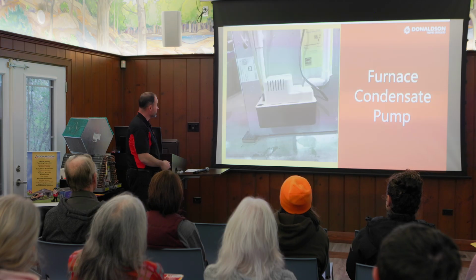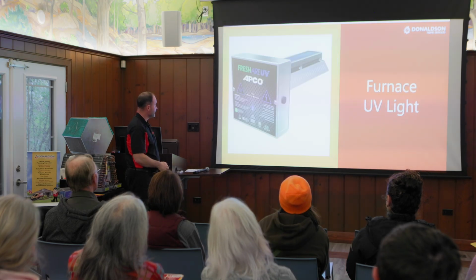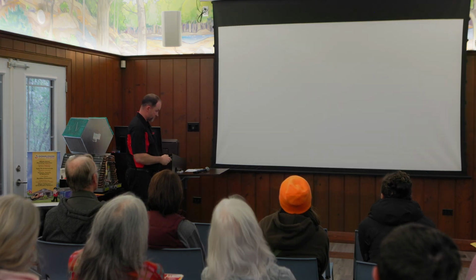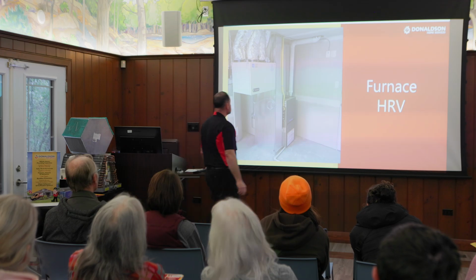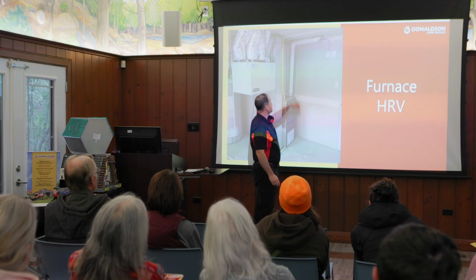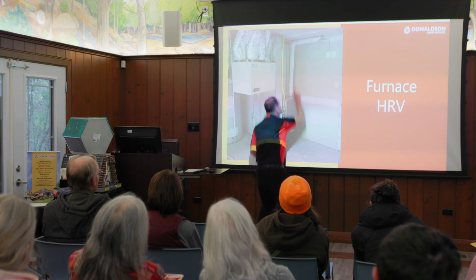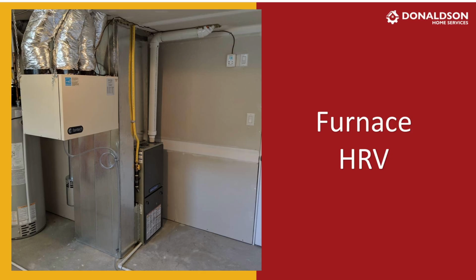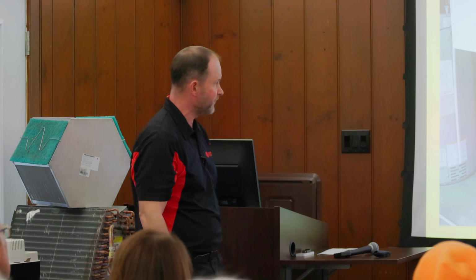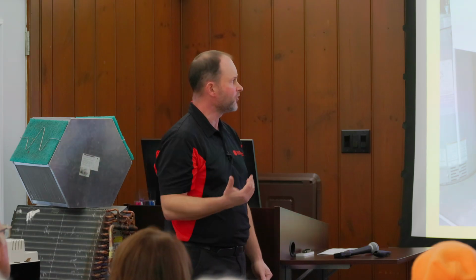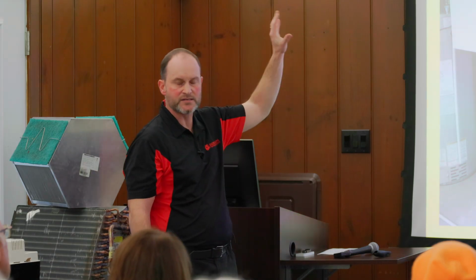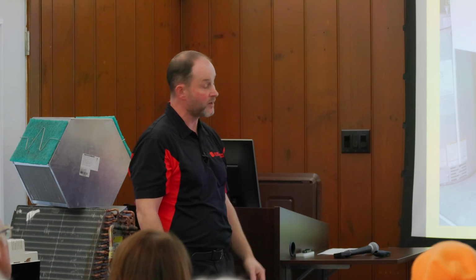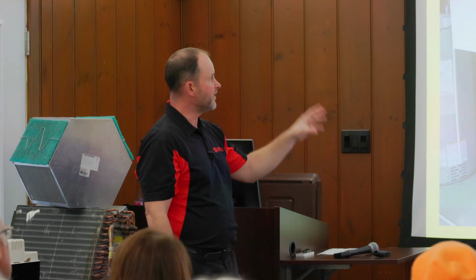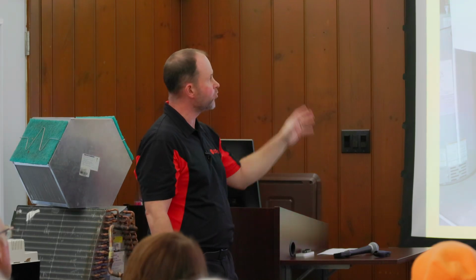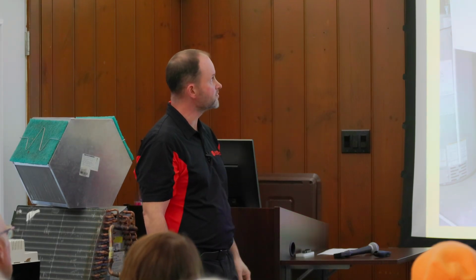With venting, I'm going to fast forward to another slide here. Try and be really fast. I'm so sorry. Venting. You have white pipe. If it's got the orange sticker on it, which is way up high on that one fitting, that tells you it's a 636 vent system. That is the appropriate vent method used. Any furnaces installed since 2007 should have that venting on it. If not, it was a no-no. But that venting is a more robust vent system with proper welding materials.